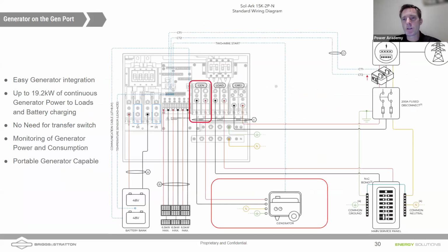If you've got the generator coming in on the gen port, this is a configuration that you would use here. So we're showing the generator coming in on the gen port, and so these are your L1 and L2. You'll also run a neutral down from the neutral bar. And you could ground that generator from a common grounding bar as well if you've got one. You could also many times pound in your own grounding rod for a generator if you're doing a whole home system. We also have the 2-wire start coming out of the comms bar and running down to the generator.